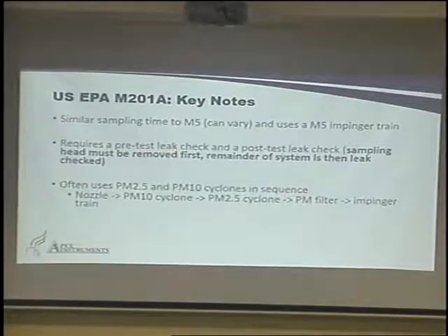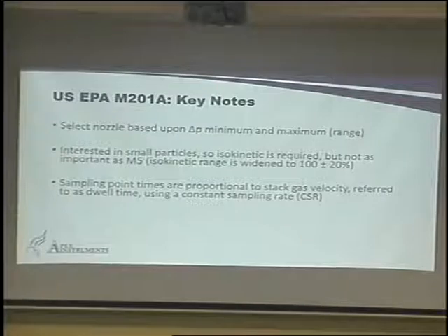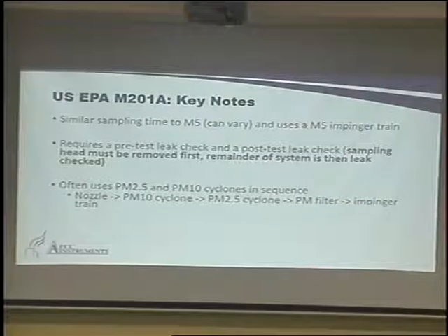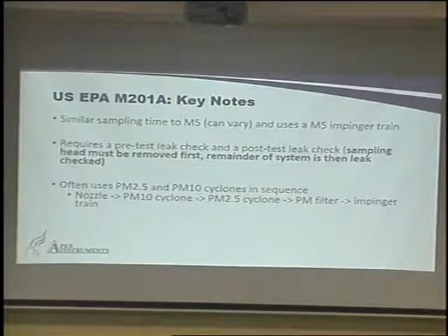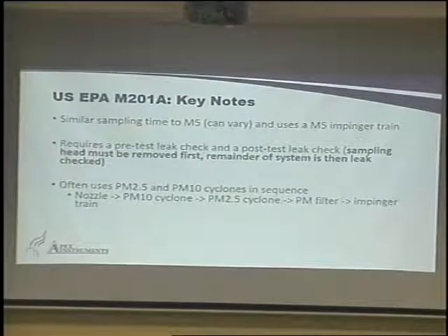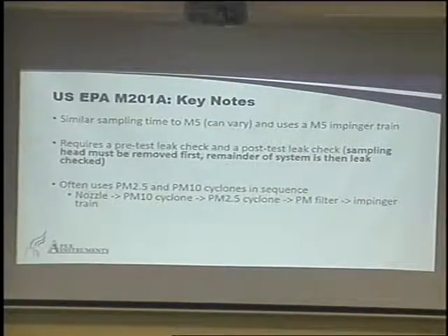And then sampling point times are proportional to stack velocity, referred to as dwell times, how long you sample at each particular point, using constant rate sampling. So everything else is the same in the back end. So your impingers are the same. The materials you use in your impingers are the same. DI water, empty, silica gel will be the same setup as method 5. We're just changing the filter from the hot box to a cyclone up the front of our probe.